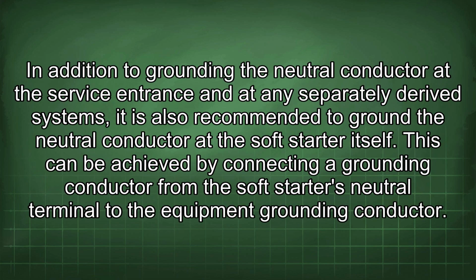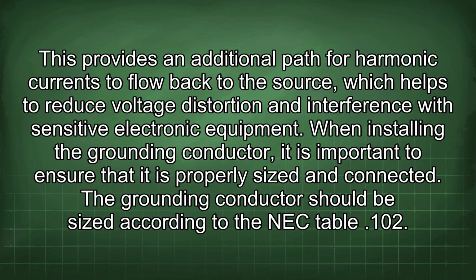In addition to grounding the neutral conductor at the service entrance and at any separately derived systems, it is also recommended to ground the neutral conductor at the soft starter itself. This can be achieved by connecting a grounding conductor from the soft starter's neutral terminal to the equipment grounding conductor. This provides an additional path for harmonic currents to flow back to the source, which helps to reduce voltage distortion and interference with sensitive electronic equipment.